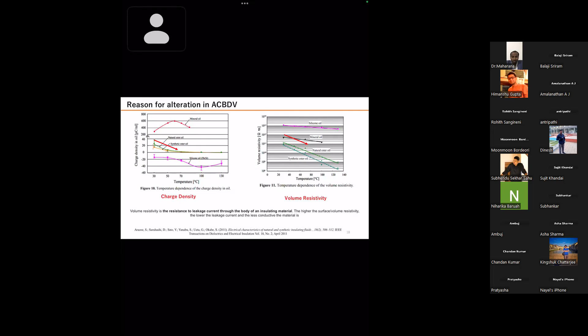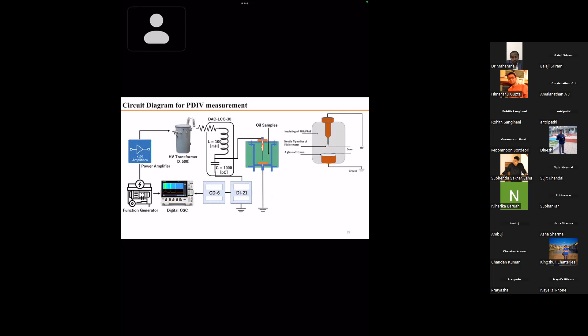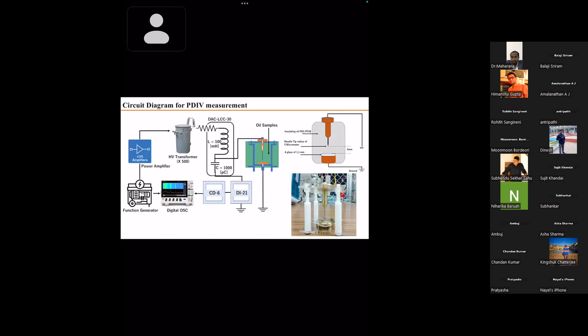Initially we got the breakdown voltage, so we need to find out the reason for breakdown. We need to understand the partial discharge inception voltage of that particular wire. So we use the needle plane electrode. You can see the circuit diagram of the entire arrangement for partial discharge.